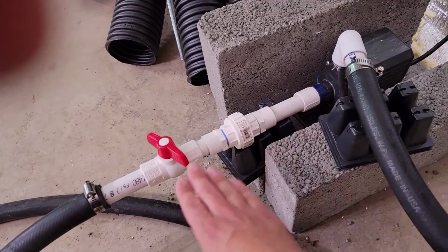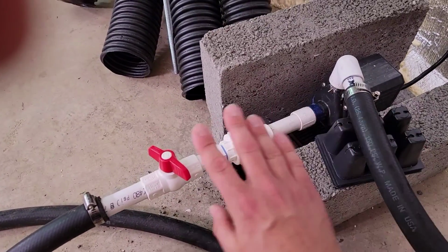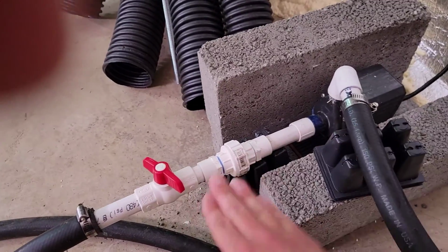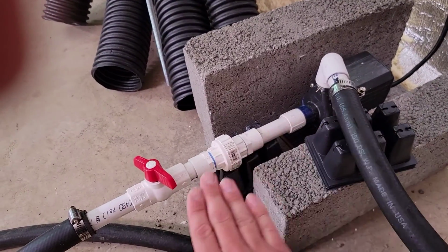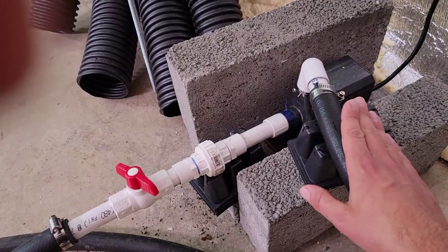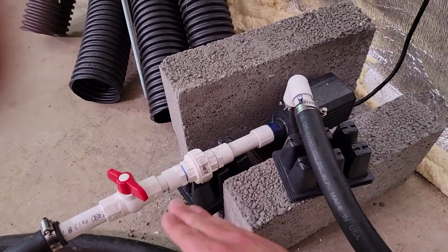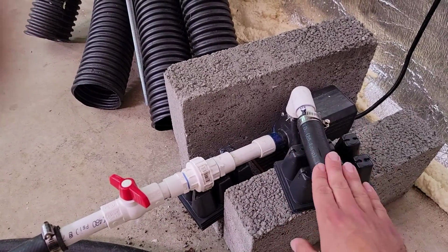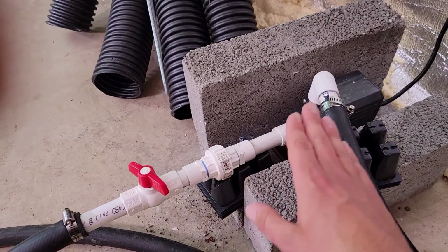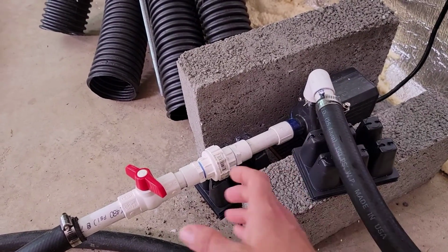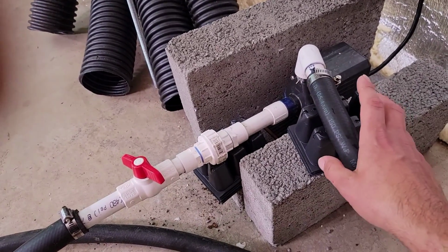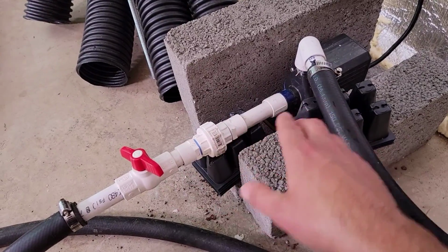Now, do I recommend this? No, because you actually affect the longevity of the pump. You affect the efficiency of the pump. The more restriction, the more resistance, the more amp draw, the less the life, okay? Get a pump that's sized properly. And if you don't know what size, go big and then cut it off. That way you at least get the temperature difference you need.